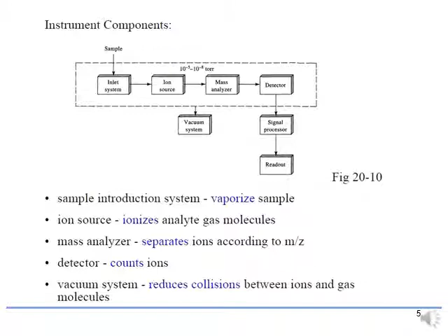In the inlet system, the sample will be vaporized. When it comes to the ion source, the analyte will be ionized. When it passes through the mass analyzer, it will separate ions according to the ratio of mass to charge. In the detector, it will count the ions, how many ions will be detected. That part will be in the detector compartment.